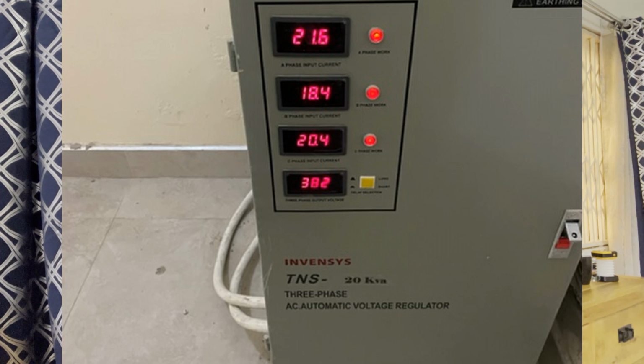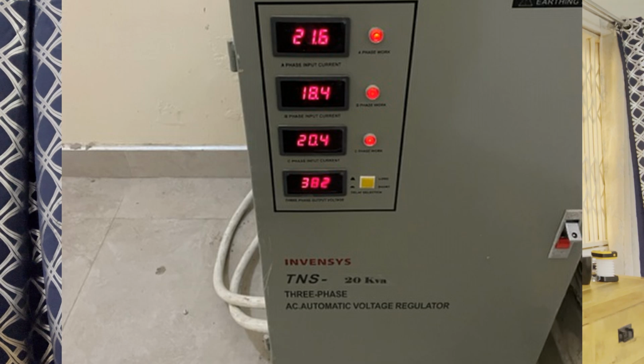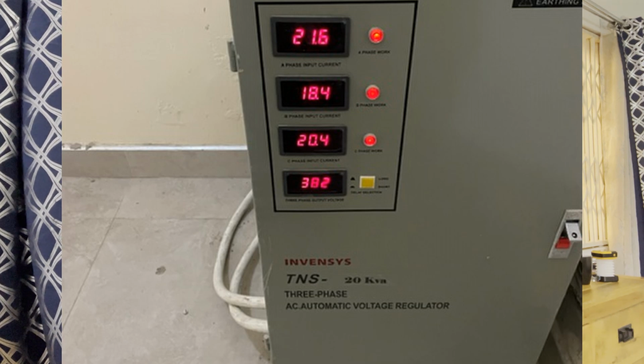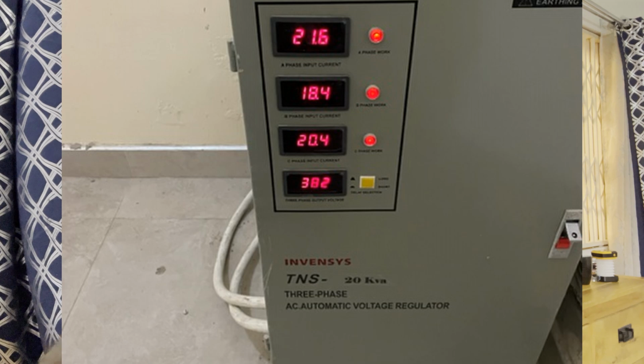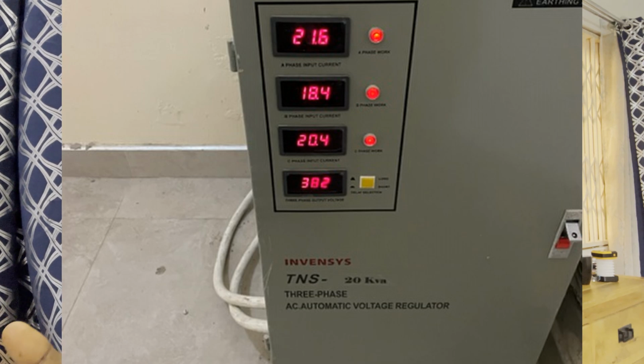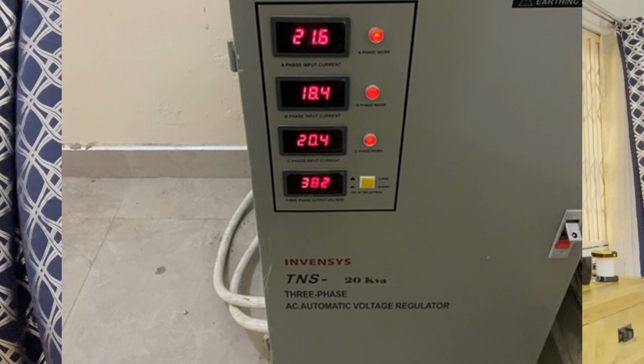So it is working. Previously they said there's something wrong with that second phase, it's not working. No, there's nothing wrong with it, it's the way you wired it. It's a machine - if you wire it correctly, it will behave correctly, as long as nothing is damaged within it. So second phase, 18.4 amps.